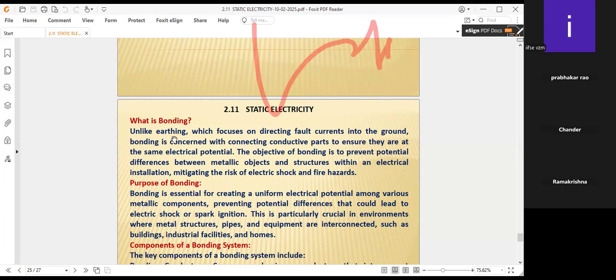Very clearly: unlike earthing, which focuses on directing fault current into the ground, bonding is concerned with connecting conductive parts to ensure they are at the same electrical potential. That means balance should be taken care of, that is the objective of bonding materials. Because electrons revolving around the nucleus in the outermost orbit are always hungry, wherever the electric charge is more in a conductive object, they will attract it. That's why the objective of bonding is to prevent potential difference between the metallic object and the structures, taking care of electrical insulation and mitigating the risk of electric shock and fire hazards.